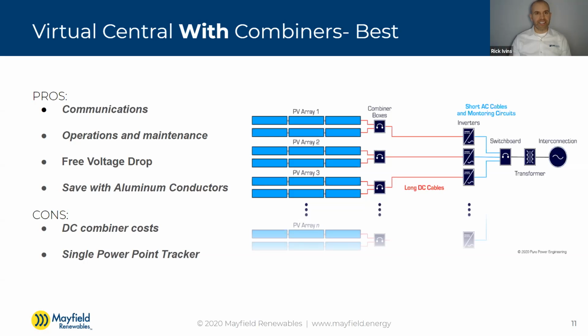Marvin Hammond always likes to talk about aluminum conductors. He gets mad when people say they're concerned about aluminum, that they've heard it's riskier than copper. As he always says, those concerns are from decades ago when aluminum first came out and there were fires back then. But the modern aluminum alloy conductors are really well made and don't have a lot of the issues people think they do at the terminations or when working with and bending them. You do want to be a little more careful when cutting away the insulation, not to nick it, but as long as you do that and have good workmanship, aluminum conductors are still great. Anyone concerned about that is probably concerned about old news, not the modern aluminum conductors.